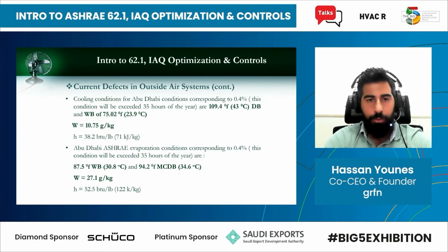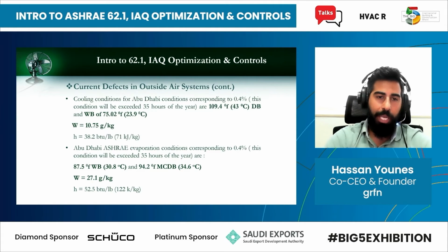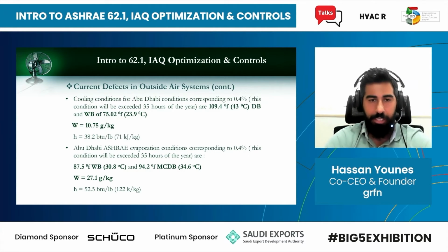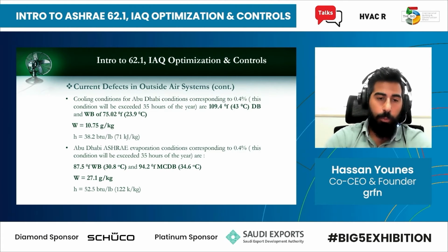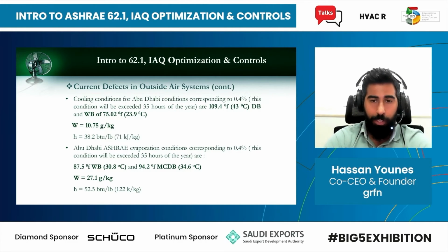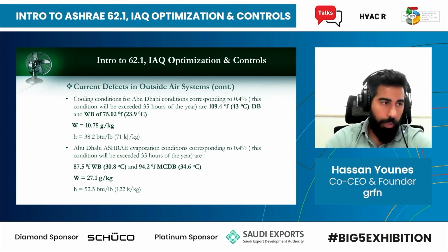So as an example, if you look at the cooling conditions for Abu Dhabi at 0.4%, meaning that this condition will be exceeded 35 hours of the year, you can see that the outdoor conditions are 43 degrees C dry bulb and a mean coincident wet bulb of 23.9 degrees C. This will result in an enthalpy of 71 kilojoules per kilogram. If you look at the evaporation conditions for Abu Dhabi, you'll find that the dry bulb is 34.6 and the wet bulb is 30.8, which is the most humid condition. And you can see that the enthalpy is 122 kilojoules per kilogram, which is much higher than the one used for the highest dry bulb, which is 43 degrees C. So you need to make sure that you're using the right conditions when you're sizing your outside air handling units.